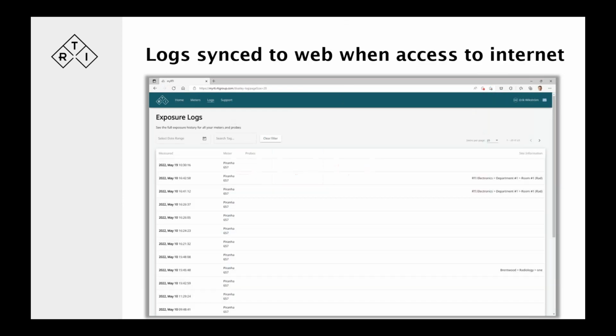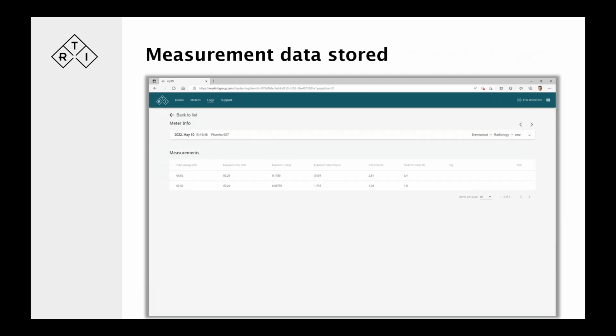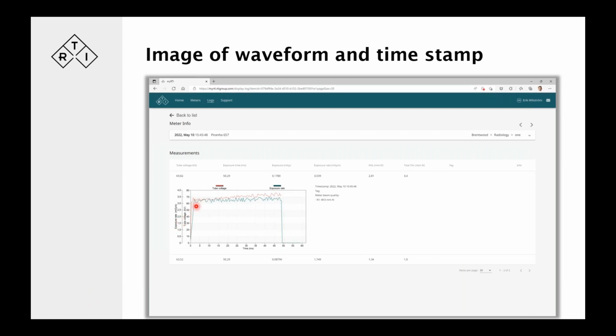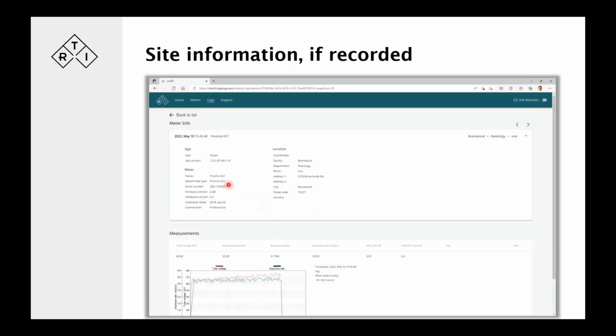And there are also the measurement logs, where you'll have a log like this created every on-off cycle of an instrument. In this case, what we see here is the Piranha that has been used. If you click on one of these rows, you'll see that in this instance, we made 2 measurements in this so-called session. If we click on the measurement, you'll have an image of the waveform. You have all the data for the tube voltage, the kV, the exposure time, everything that was recorded, when it was made, a timestamp, and what beam quality was used for that specific measurement. If there was location information, if there was site information associated with this measurement, it will also show up here, where that was made, which facility it was at. But that's only if that information is available at the time of exposure.